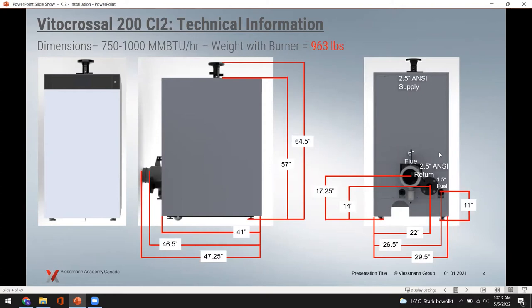The 750,000 to 1,000,000 BTU boilers are still single burners and weigh up to 963 pounds. The depth increases to 47.25 inches due to more plates and more heat exchange surface area, but the width stays the same at 29.5 inches, so it still fits through a standard door. The height is still under six feet, so you won't need a ladder for service. It's really easy to wire the back and do service at the front.